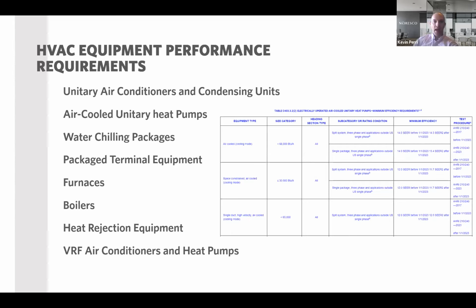So if you look at furnaces or boilers or water chilling packages, air-cooled heat pumps, those tables have been updated in the new 2021 version of the code. I will spare you the thrill of posting all those and going through all those, but I did put a snippet on the screen there. I know it's kind of hard to read, but just to show you that for some of these categories of systems, the efficiencies have increased, or some sort of item in that table has changed in the 2021 code, which is expected. We can't get towards our energy efficiency goals if we don't increase efficiencies on some of our equipment.